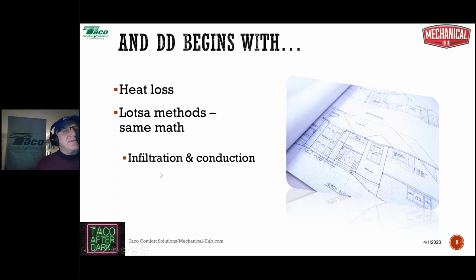And what those math formulas measure is infiltration, which is air leakage. Heated air leaks from inside to outside. It's replaced by cold outside air. We have to heat that up. And then there's conduction - heat loss via conduction, energy transferring from a warm surface inside to a cooler surface outside, through walls, through windows, floors, ceilings, doors, etc. We're going to show you how to do both of those things. At best, folks, heat loss is an educated estimation. We have to build in a lot of assumptions.